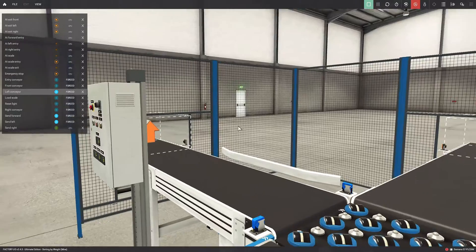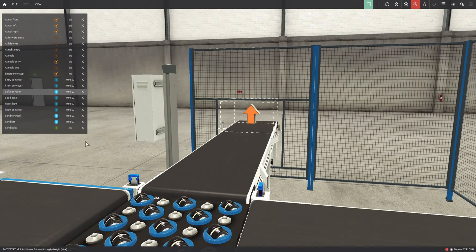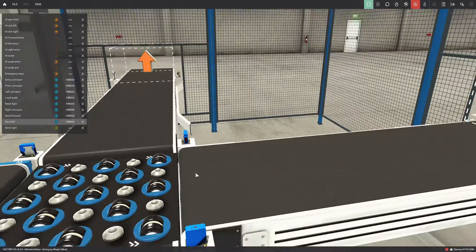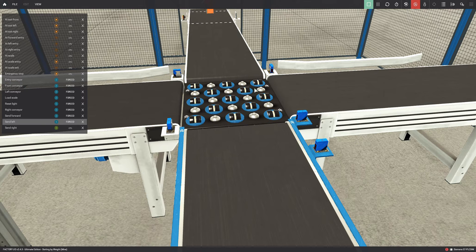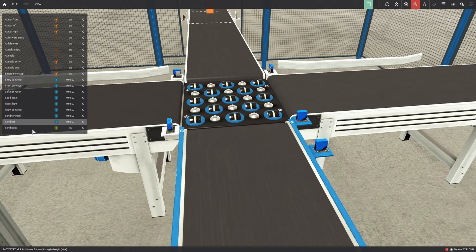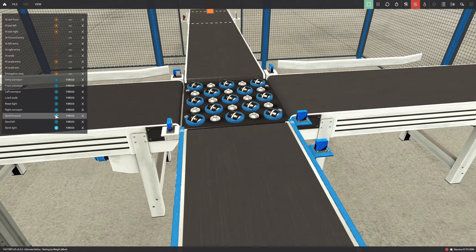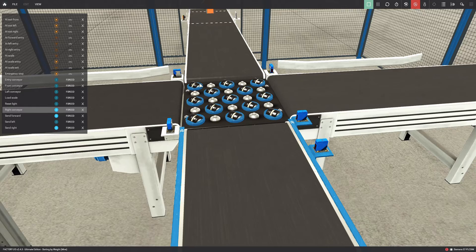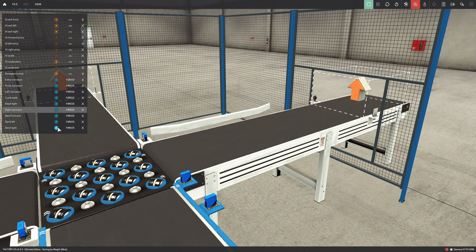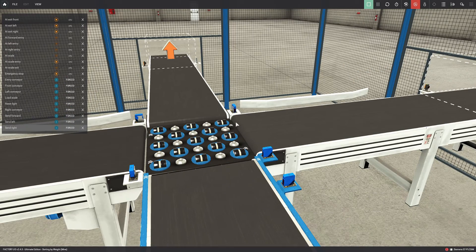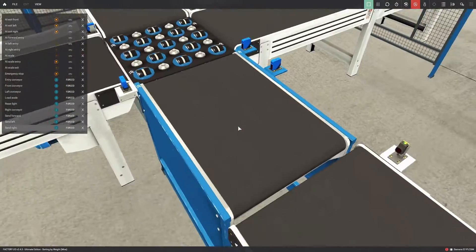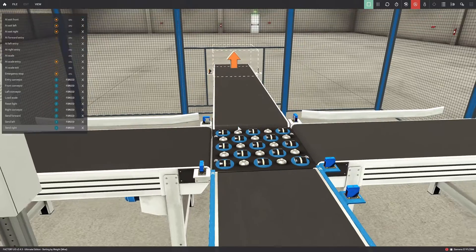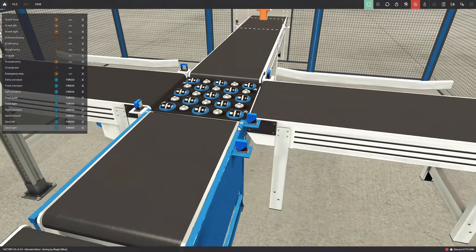Then what we can do is when the piece reaches that sensor, that photocell there, the rollers separate and return to their original position. This would be a cyclical process. And if the box weighs more, if it's 7.5, then the same but to the right, which would be with Send Right. We'd activate the rollers and also activate the right conveyor. When it arrives there, everything deactivates. This should always function the same way, cyclically. So this would be the basic operation - how the boxes or pieces arrive and are distributed to one side or the other.